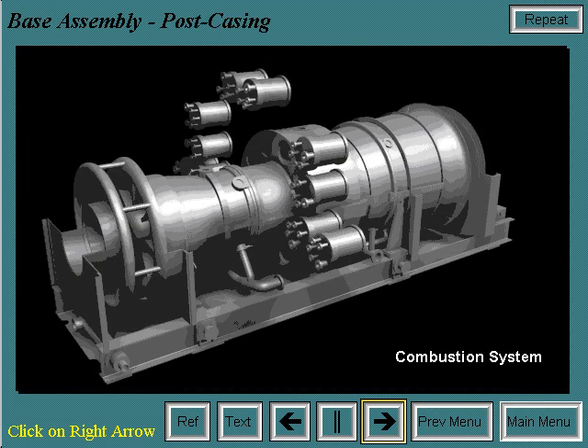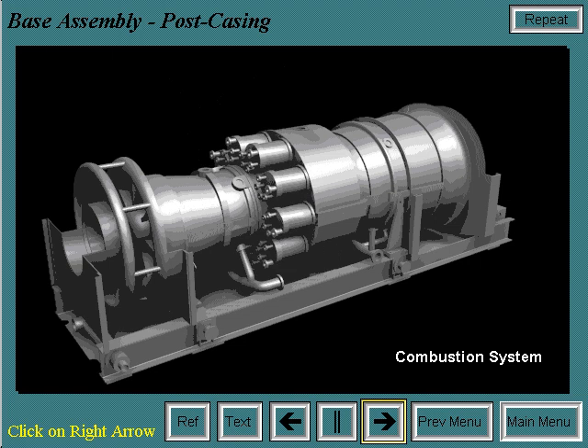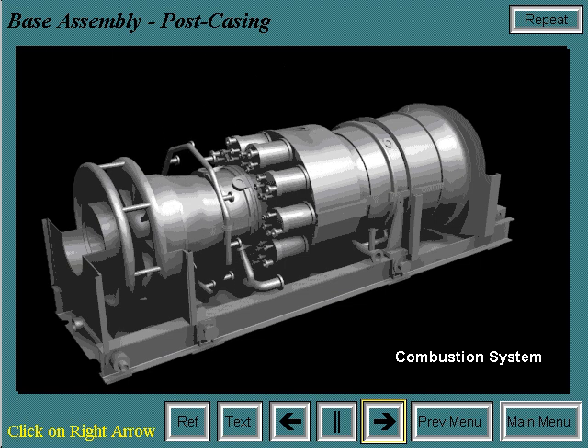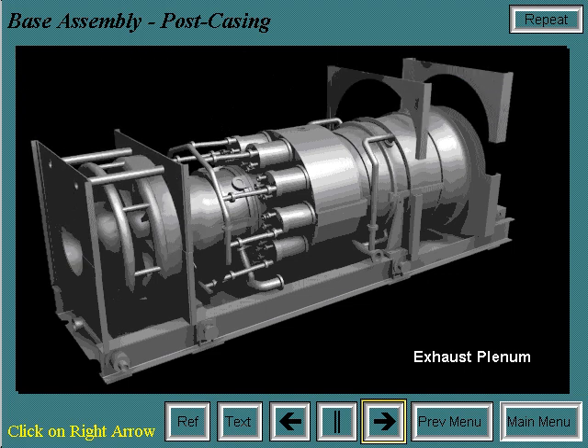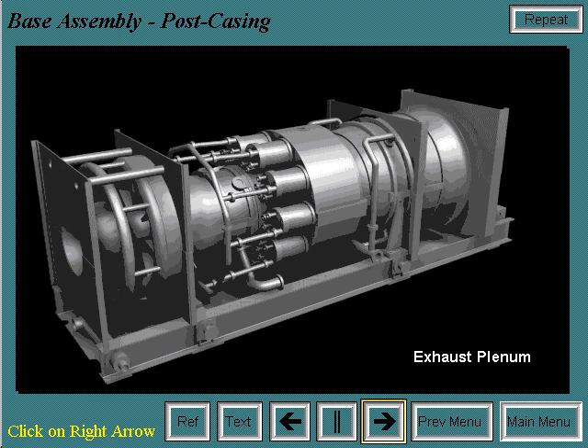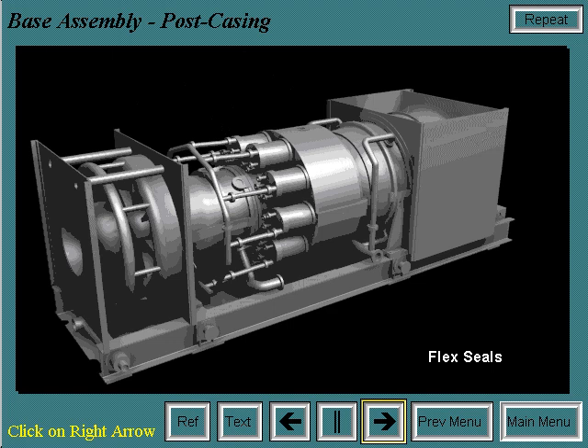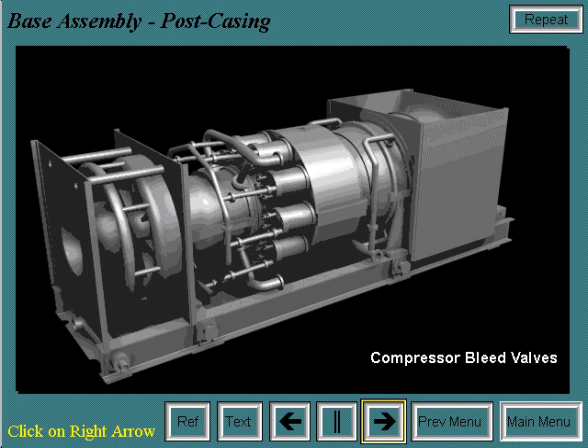Once the casings are on, the combustion system is installed. Next, the shell cooling air piping is installed. Air comes from off-base blowers to facilitate shell cooling in the turbine and exhaust casings. Then the inlet plenum is installed, and after this the exhaust plenum is put in place. The flex seals keep the exhaust gases from escaping into the turbine compartment or out to atmosphere while allowing for thermal expansion. Finally, the compressor bleed valves are installed.